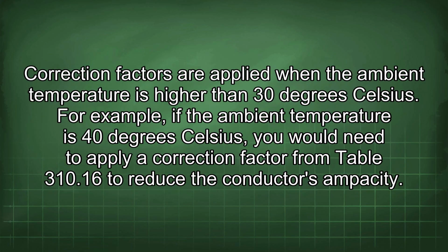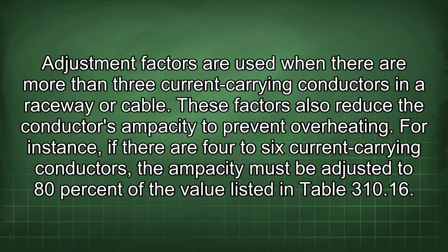Correction factors are applied when the ambient temperature is higher than 30 degrees Celsius. For example, if the ambient temperature is 40 degrees Celsius, you would need to apply a correction factor from Table 310.16 to reduce the conductor's ampacity. Adjustment factors are used when there are more than 3 current-carrying conductors in a raceway or cable. These factors also reduce the conductor's ampacity to prevent overheating.